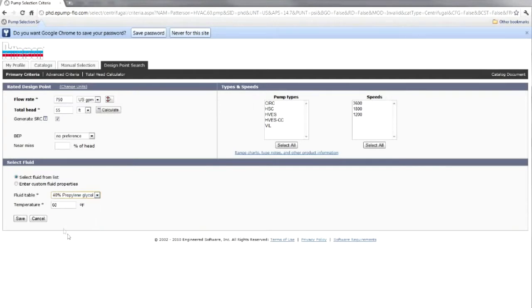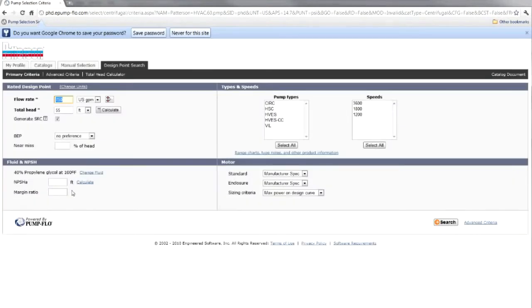Now the temperature, as I mentioned before, is critical with your glycol. The colder your glycol solution, the more viscous it becomes. The hotter it is, the more it tends towards the conditions of water. So let's change this temperature. It's a hot water heating system, so the coldest it will ever operate typically is maybe 100 degrees. And we'll save that, and now that plugs in and changes the properties of our fluid.